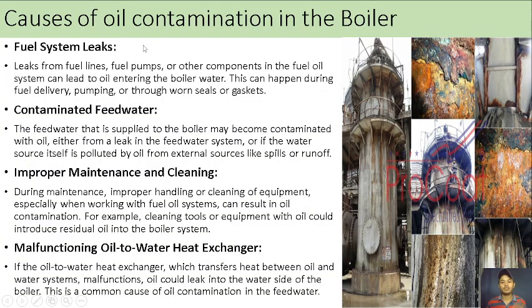Okay, so causes of oil contamination in the boiler. We have fuel system leaks. Leaks from fuel lines, fuel pumps, or other components of the fuel oil system can lead to oil entering the boiler water. This can happen during fuel delivery, pumping, or through worn seals or gaskets. Contaminated feed water: the feed water supplied to the boiler may become contaminated with oil, either from a leak in the feed water system or if the water source itself is polluted by oil from external sources like spills or runoff. Or maybe there is leakage in your feed water consumers, so there will be contaminated feed water also.